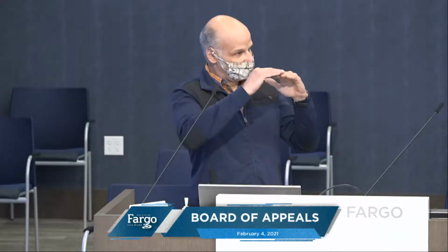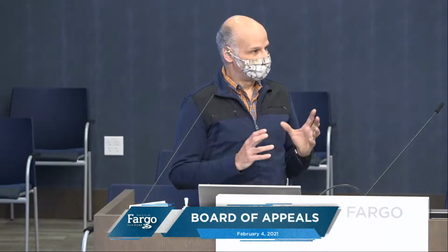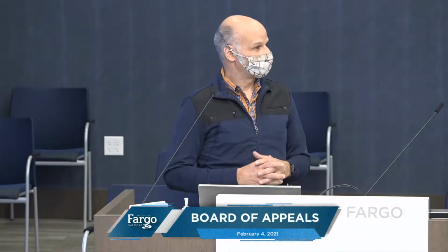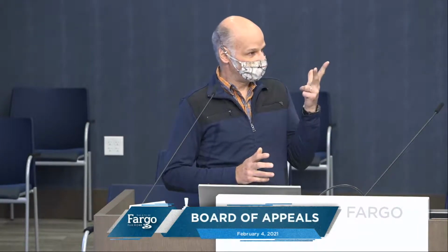I'm sorry, which one garage to the other are you referring to? One tier of garages. It does not say that you can, with that opening you created with the ramp, calculate those numbers from this tier to this tier and exceed the 1,000. Does it say that anywhere, or am I missing something? It says each garage unit shall be not more than 1,000 square feet. Each. Indeed, we have 3.